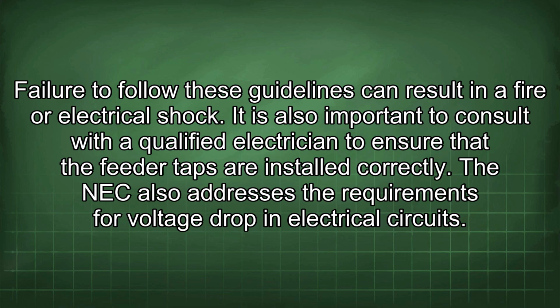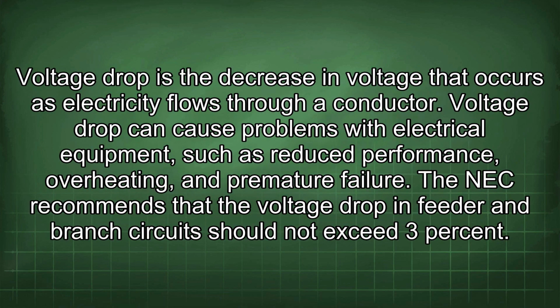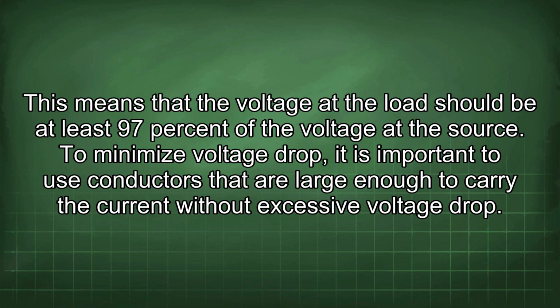The NEC also addresses the requirements for voltage drop in electrical circuits. Voltage drop is the decrease in voltage that occurs as electricity flows through a conductor. Voltage drop can cause problems with electrical equipment, such as reduced performance, overheating, and premature failure. The NEC recommends that the voltage drop in feeder and branch circuits should not exceed 3%. This means that the voltage at the load should be at least 97% of the voltage at the source. To minimize voltage drop, it is important to use conductors that are large enough to carry the current without excessive voltage drop.